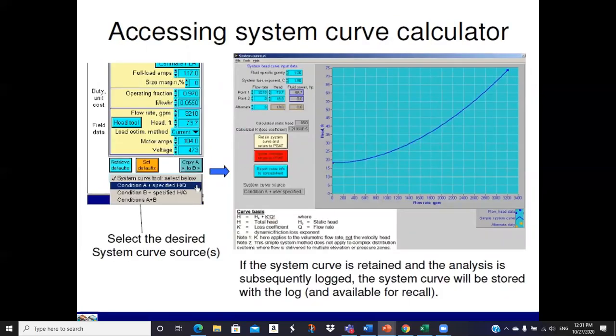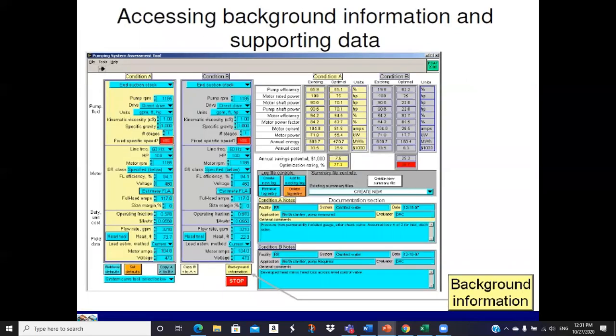This is the system curve calculator. There is one of these in Measure as well. Let me go back. Here, it's right here. That's a pull down, and it'll ask you, do you want to fit a system curve for condition A, condition B, or both? Doesn't really matter. If you tell it to, it will feed numbers back in for a head, or you can just use the equation, get a head, and punch it in there. Either way.